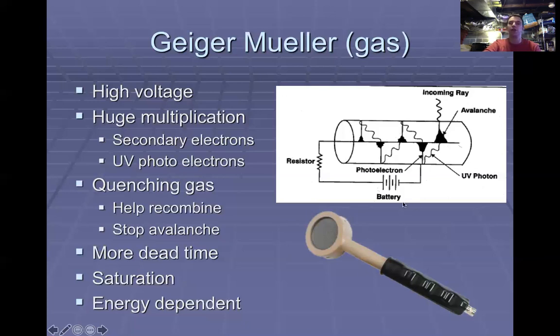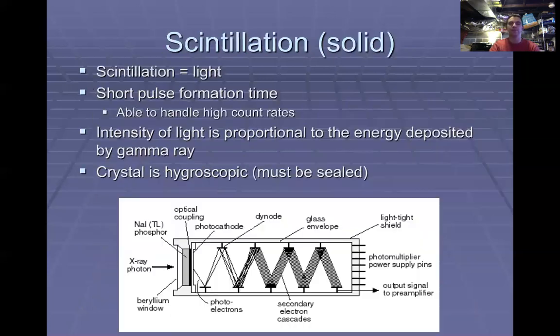You really don't want to try to get dose rate with them, because depending on the energy of the radiation they are detecting, they can give wildly different dose rate estimates. You can be off by a factor of 100 or more. So if you're trying to quantify radiation and you have a meter that is incapable of being accurate to less than 100 times, it's essentially useless. The difference between 2 mR and 200 mR per hour is a pretty big difference when you're talking about safety. So that's why we never use these meters for dose rate readings.